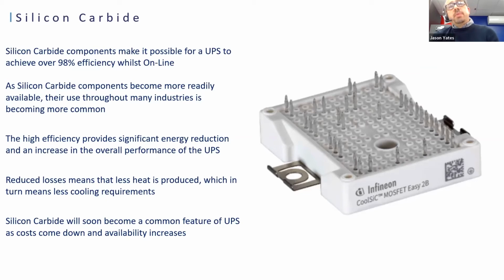The benefit of silicon carbide components is that they're becoming more readily available, and their use throughout many industries is becoming more and more common. Again, the high efficiency these components provide significantly reduces the overall cost of operating a UPS and increases the overall performance of the UPS system. In conjunction with this, the reduced losses mean that less heat is produced by the UPS system, which in turn means less cooling on site. So effectively, with the UPS systems of the future, you will see more and more coming through with silicon carbide options, and eventually it will all be silicon carbide as the price comes down and the availability increases.